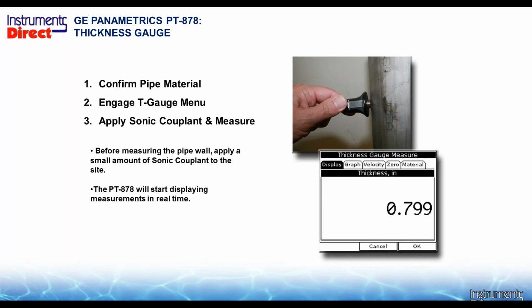And now we're going to install the device. In this case, we need to put on your thin sonic couplant. This is not an application where you want to use your silicone grease, not just because of the thickness of it. We want metallic contact to metallic contact. It's just a small film transferring the sound from the face of the thickness gauge to the pipe wall itself. So the key is to apply your couplant to the face of the thickness gauge and press it on the pipe so you have mechanical contact there. Don't wick it up. Don't squeeze it up or pull it away from there, because it may also see the sound beam through the wicking and the pipe wall thickness, and it could give you an erroneous reading.